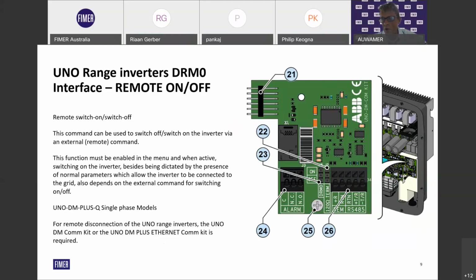So as you can see here, there's a few different terminals on the COM kit for RS485 through Modbus RTU communication. So ideal for connecting an energy meter for any zero export or export limitation. Also alarm contacts for its completely configurable alarm, as well as can be configured as a load management relay. And then we have the remote on-off, on terminal number 26 there. So this is a digital input into the inverter. It is quite simple. How it works is all we're really doing is bringing one terminal of the remote on-off to the same potential as the other terminal, which activates the digital input. So before we move on, it's important to know that with the UNO DM range, you will require the UNO COM kit to activate the DRM0.